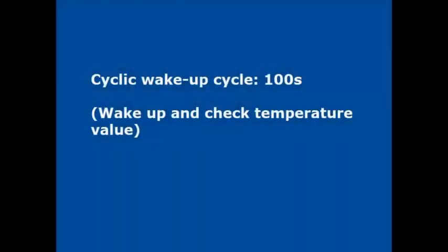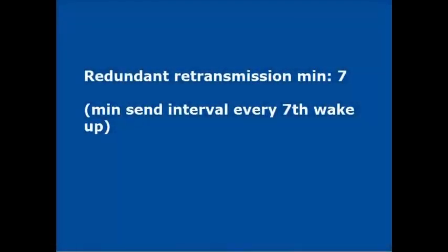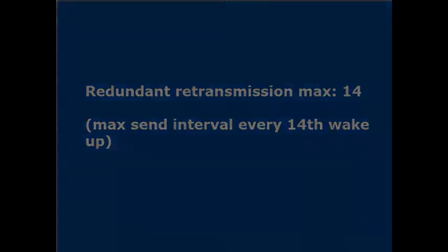Cyclic wake up cycle, 100 seconds: wake up and check temperature value. Redundant retransmission minimum, 7: minimum send interval every 7th wake up. Redundant retransmission maximum, 14: maximum send interval every 14th wake up.